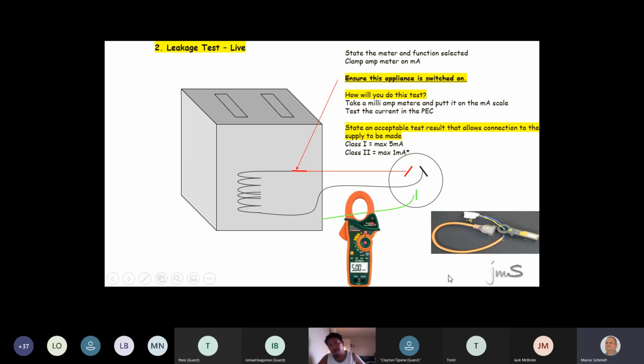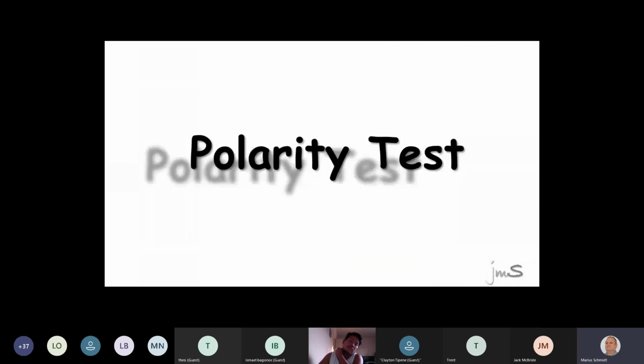Now we find out that that's an old lead we used to have. Now we're running double insulated conductors from a plug to a lead and we make up our own little short lead. Now guys, this rule is only applicable to appliances. All right? Cool. Are you okay so far? So we did earth continuity, insulation resistance. Now polarity. Come on guys, it's only 4 more to go.